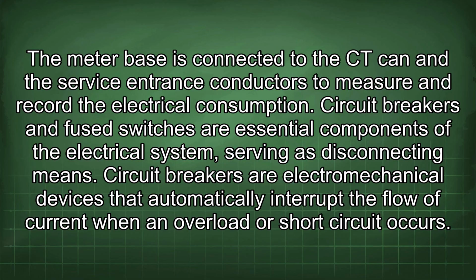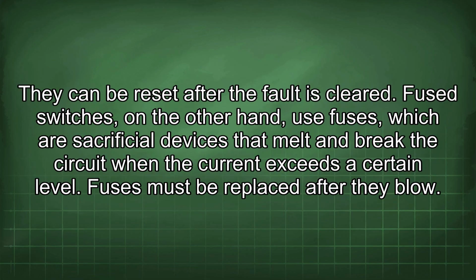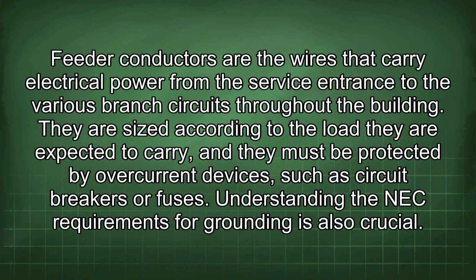Circuit breakers are electromechanical devices that automatically interrupt the flow of current when an overload or short circuit occurs. They can be reset after the fault is cleared. Fuse switches, on the other hand, use fuses, which are sacrificial devices that melt and break the circuit when the current exceeds a certain level. Fuses must be replaced after they blow. Feeder conductors are the wires that carry electrical power from the service entrance to the various branch circuits throughout the building. They are sized according to the load they are expected to carry, and they must be protected by overcurrent devices, such as circuit breakers or fuses.